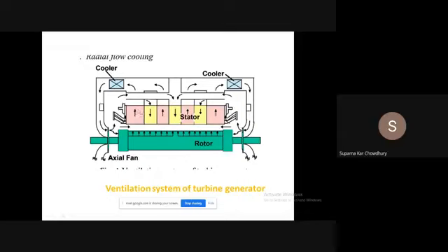But the conductivity in this transverse direction and in the radial direction is not the same. Particularly from the slots, there will be the insulation, which is a bad conductor, so the conduction of heat to the duct is not very good.